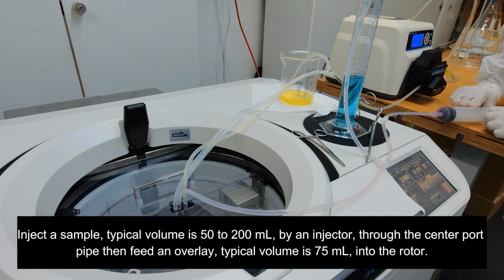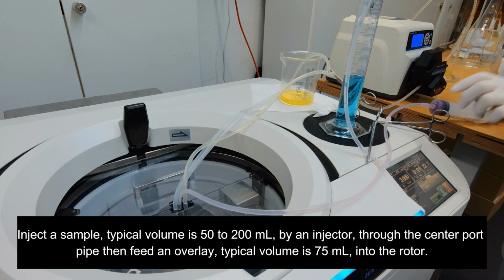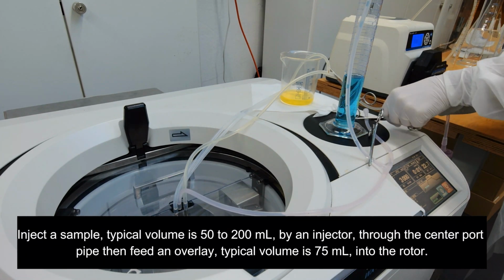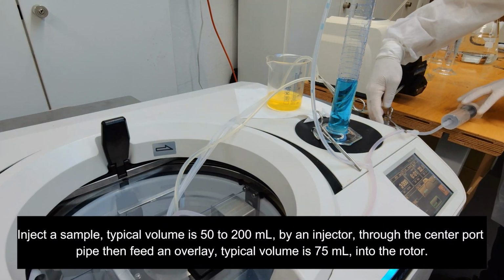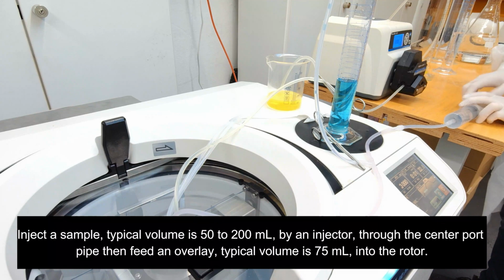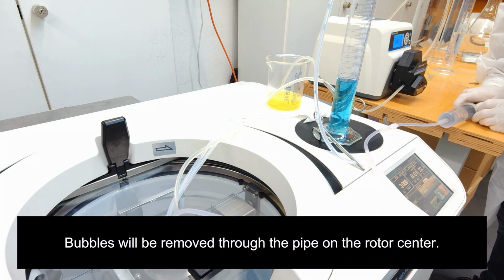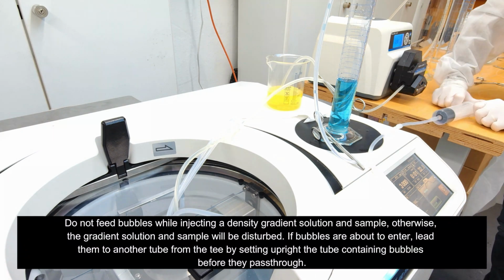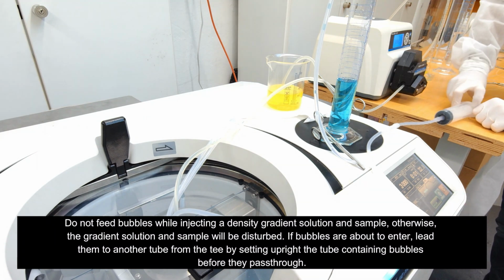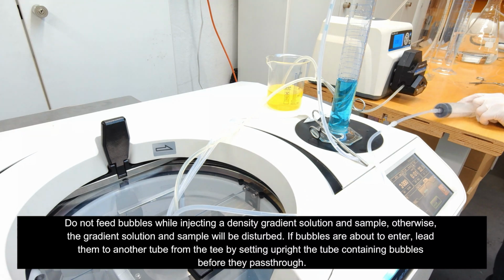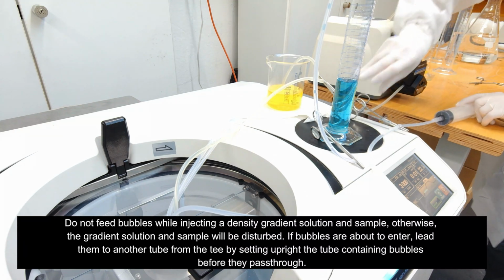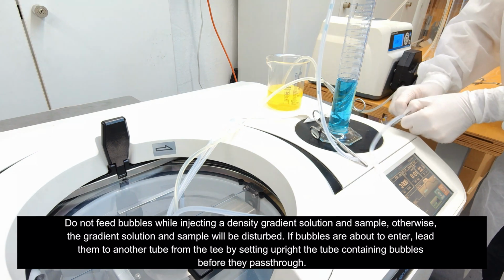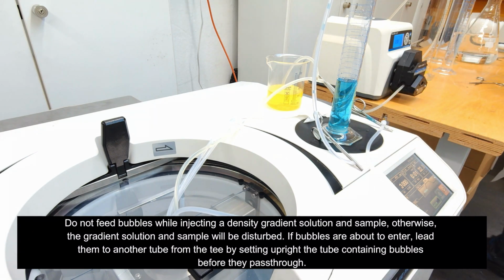Inject a sample, typical volume is 50 to 200 milliliters, by an injector through the center port pipe, then feed an overlay, typical volume is 75 milliliters, into the rotor. Bubbles will be removed through the pipe on the rotor center. Do not feed bubbles when injecting a density gradient solution and sample, otherwise the gradient solution and sample will be disturbed. If bubbles are about to enter, lead them to another tube from the T by setting upright the tube containing bubbles before they pass through.